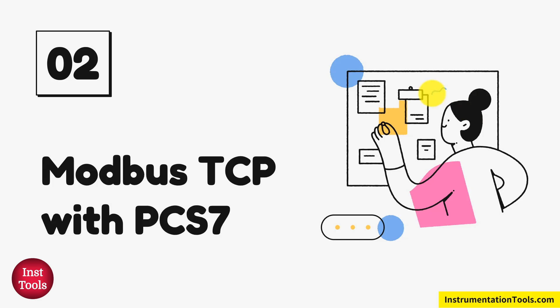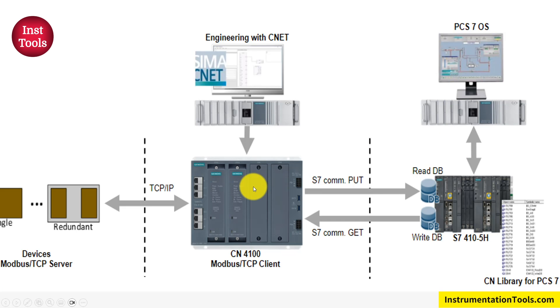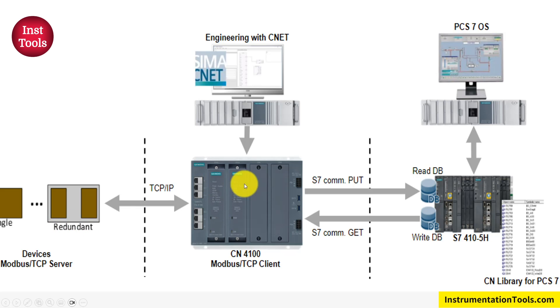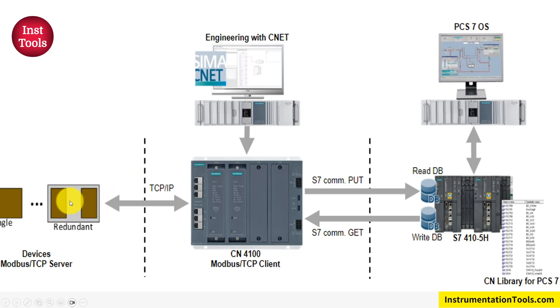Next comes Modbus TCP, which follows Ethernet principles. The solution offered by Siemens is the CN4100, which is mainly a Modbus TCP client that takes data from Modbus TCP servers. Since this is a TCP/IP protocol, devices are termed as server and client. On the left side, there are single or redundant Modbus TCP server devices with IP addresses such as 192.168.0.x. The CN4100 is available in single and redundant configurations. Configuration and software control is done using the engineering station software CNET, which is used to program the CN4100 to configure which TCP servers it needs to pull data from.